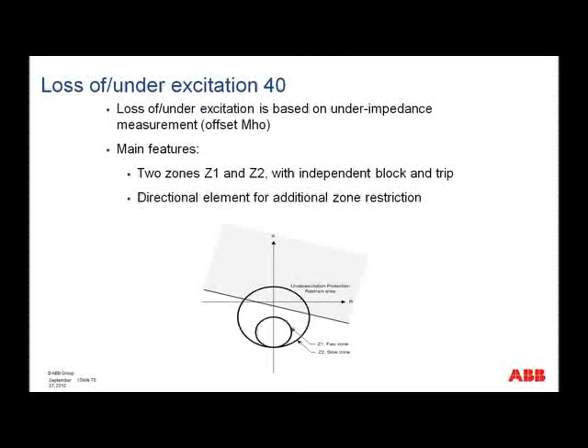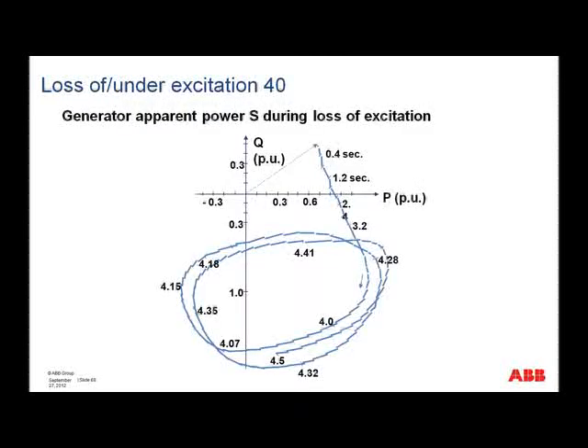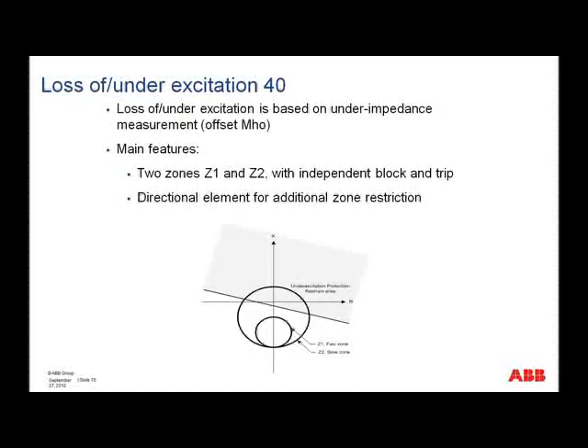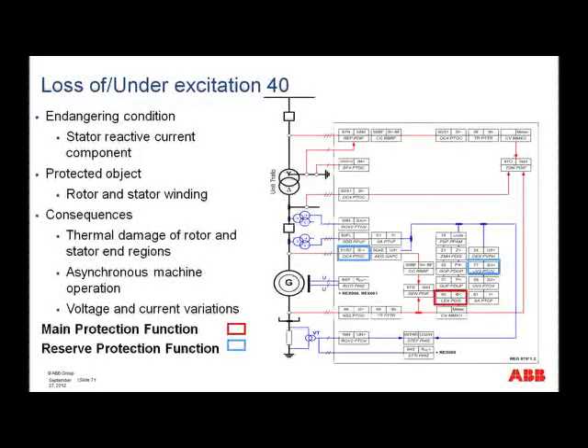Now, one thing just to bear in mind is that if we look back at this slide, which was drawn in the PQ plane, and you can see where the locus is, and we look at this picture, it looks like, of course, that we have the underimpedance protection in exactly the right place. But just remember that this is shown in the XR plane, and if we want to convert from the S to the Z plane, really it's only valid for fixed voltage, and of course in circumstances of loss of excitation, the voltage is not constant. But nevertheless, I guess over years of experience, this has been shown to be the best protection to handle such loss of excitation.